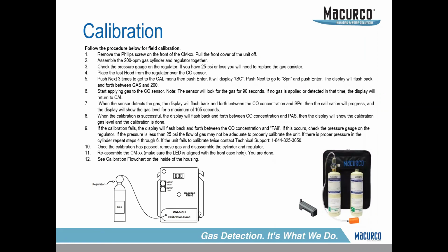Here's our calibration process — I'm not going to go through the whole process, but I'll show you it takes about 1.5 minutes per detector. On the bottom right you have your canisters of gas, a regulator and tubing. You connect that little orange hood, or gray hood in this case, right over your sensor and start your calibration process. Again, about 1.5 minutes — it's in and out, pretty efficient.